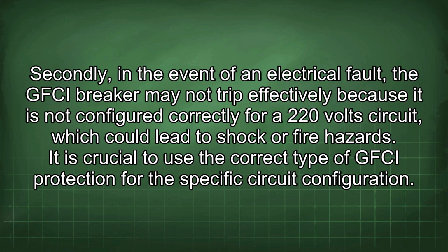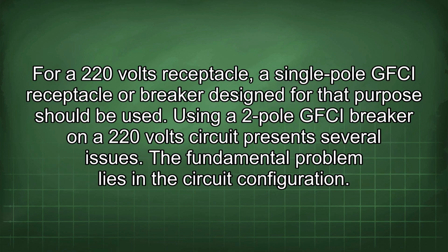It is crucial to use the correct type of GFCI protection for the specific circuit configuration. For a 220 volts receptacle, a single-pole GFCI receptacle or breaker designed for that purpose should be used. Using a 2-pole GFCI breaker on a 220 volts circuit presents several issues. The fundamental problem lies in the circuit configuration.